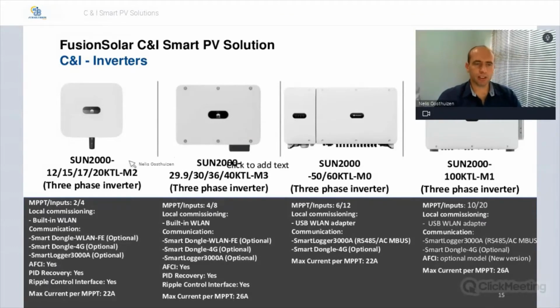The first slide is actually a comparison between all the different ranges that's available. The first range would be from 12 to about 20 kTL M2. The M is to indicate that it's a three-phase inverter, and the 2 is the revision number. So this was the second revision of the specific range of inverter. So this is typically your smallest range of commercial and industrial inverters. Anything less than the 12 kTL, so going through to a 10 kTL M1, Huawei sees that as a residential installation. Our next segment would be the 29.9 or the 30 kTL all the way to 40 kTL.